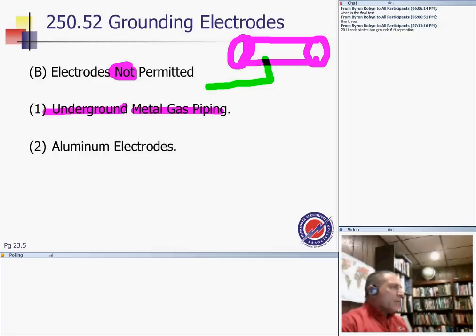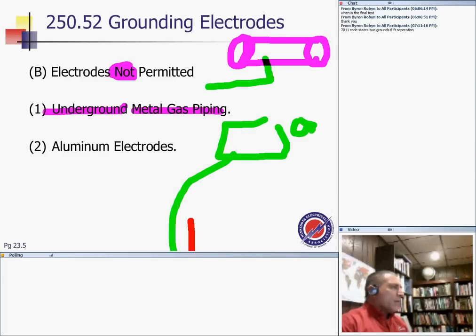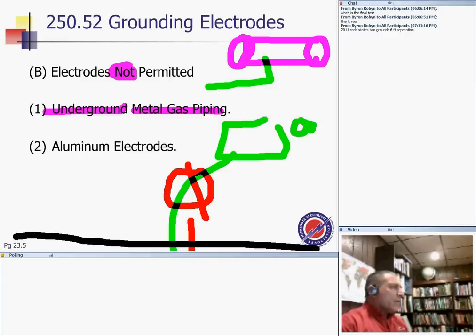Now the same gas pipe, if you have a gas pipe that's coming to your house and entering the house right in here, and this is bringing your neutral, your grounding system, here's my ground. This is called a no-no. You can't do that if it's underground. If above ground, you have to bond it. This is underground, this is Earth, Mother Earth, right in here. This is above ground. Any questions, guys, about bonding above ground and not underground?